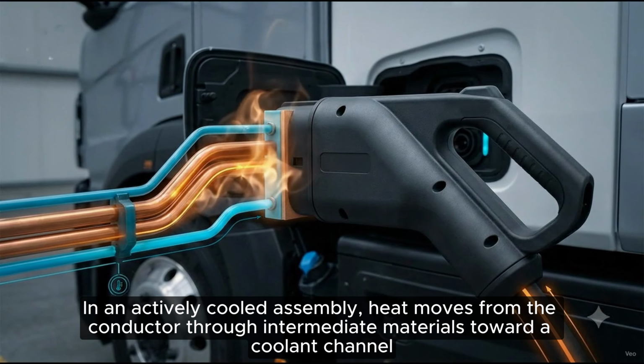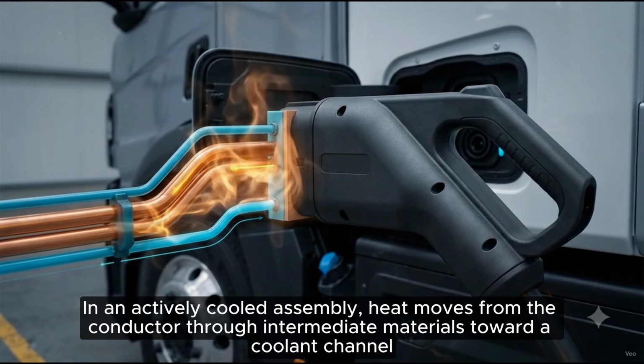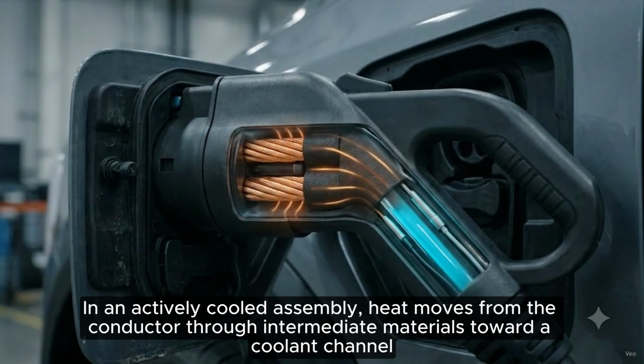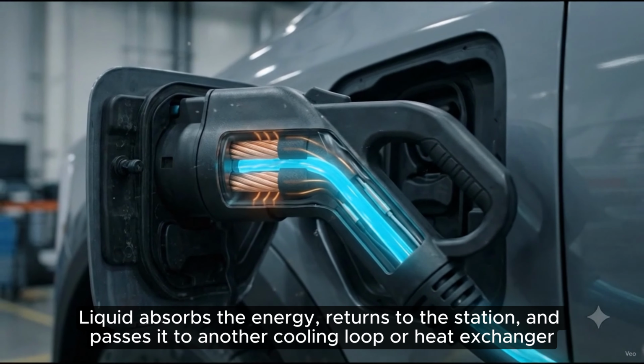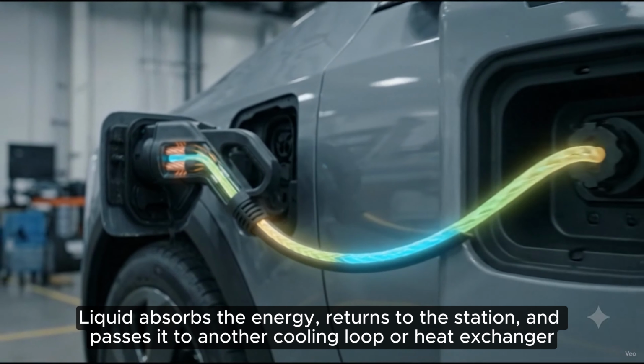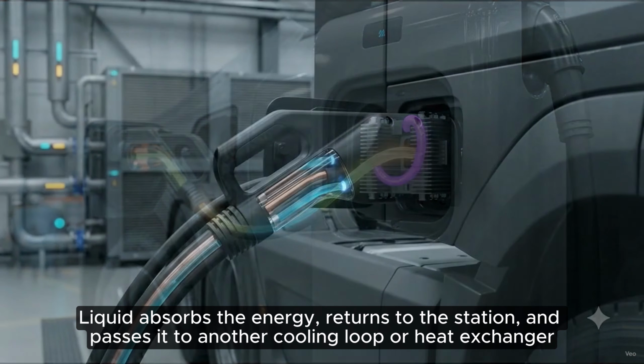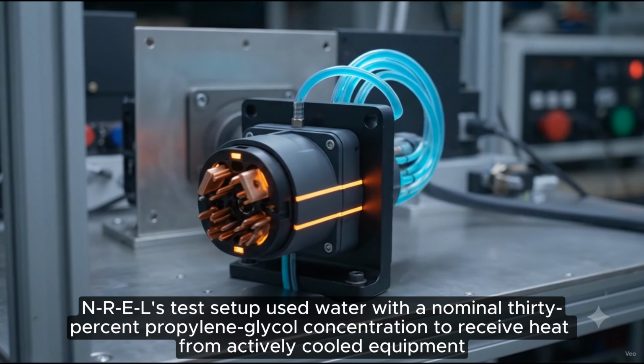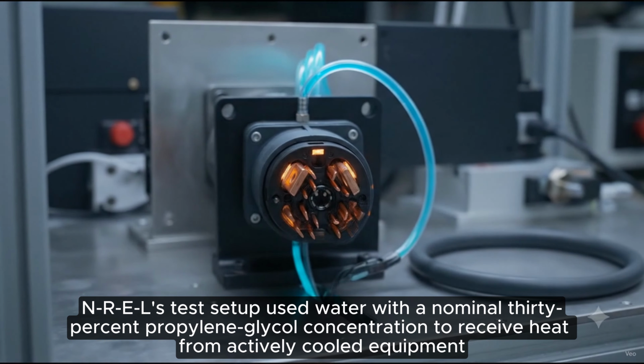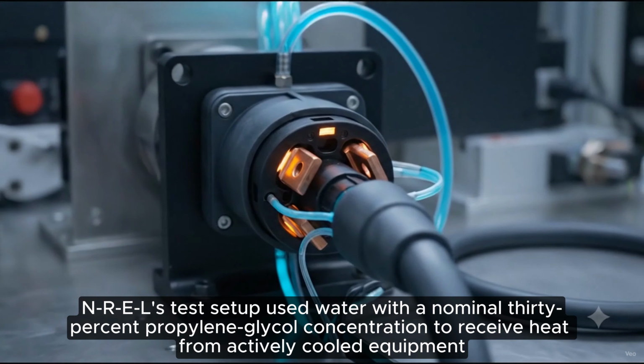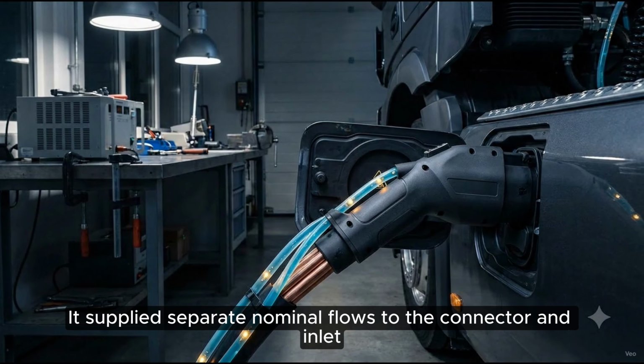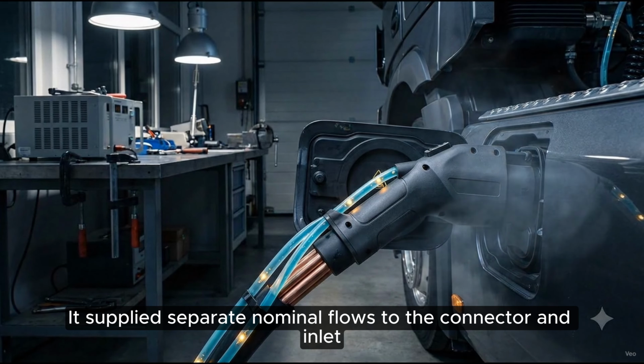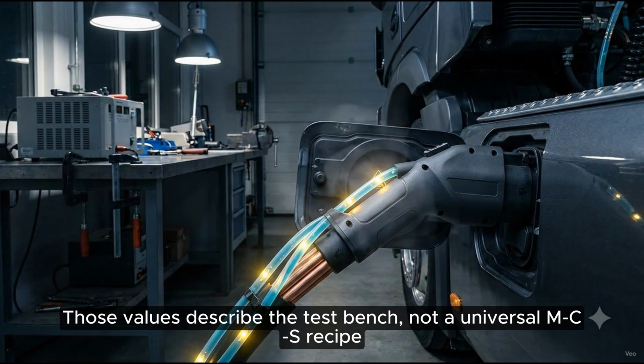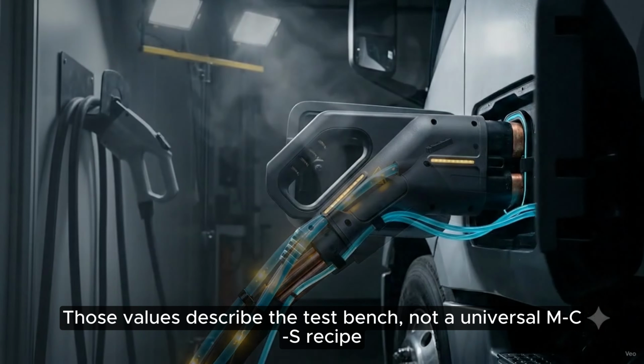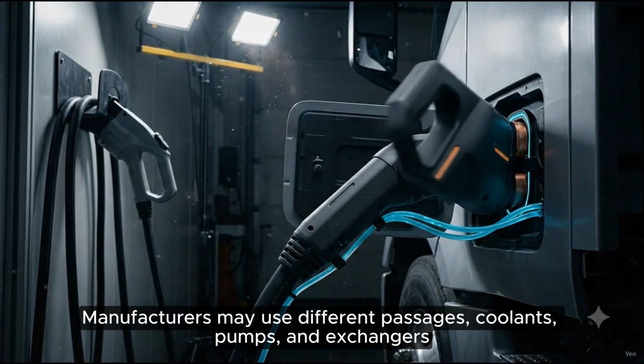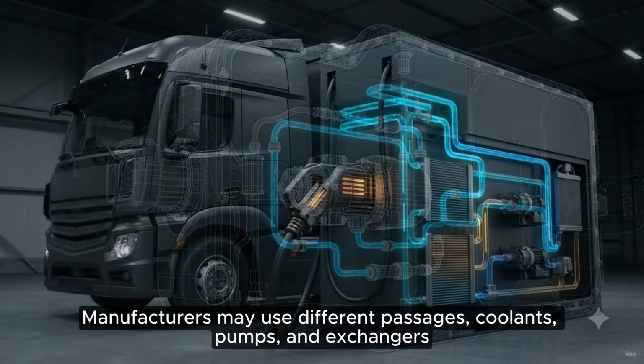In an actively cooled assembly, heat moves from the conductor through intermediate materials toward a coolant channel. Liquid absorbs the energy, returns to the station, and passes it to another cooling loop or heat exchanger. NREL's test setup used water with a nominal 30% propylene glycol concentration to receive heat from actively cooled equipment. It supplied separate nominal flows to the connector and inlet. Those values describe the test bench, not a universal MCS recipe. Manufacturers may use different passages, coolants, pumps, and exchangers.